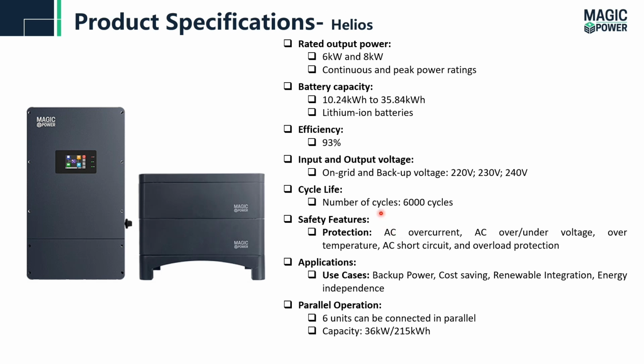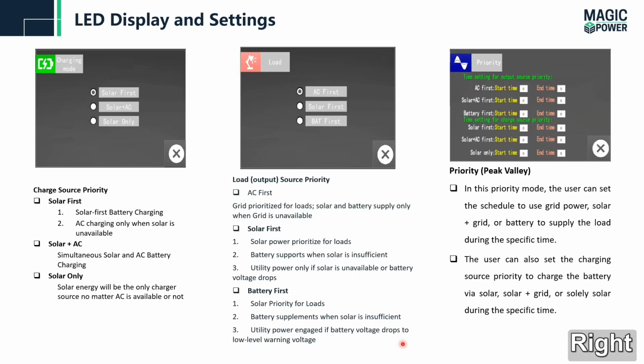The life cycle of the battery is 6000. Safety features: over current, over and under voltages, over temperature, and short circuit and overload protection. These are the integrated protection features of this system. Application scenarios for these systems are backup power, energy independence, and cost saving. Parallel operation, as I mentioned earlier, allows a maximum of 6 units in parallel. The rated output power for the system will be 36 kilowatts, while the storage capacity will be 215 kilowatt hours. So next we'll learn some settings of the system.